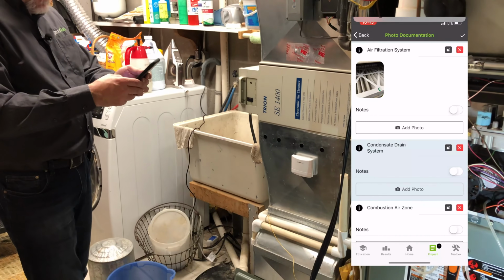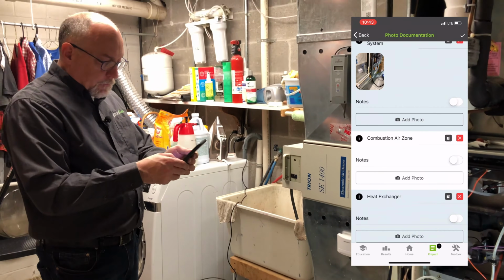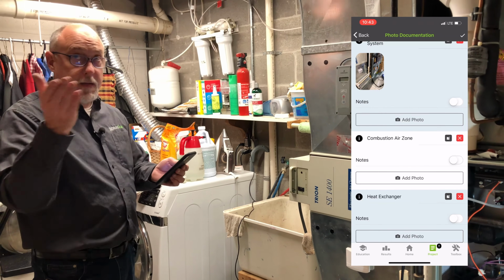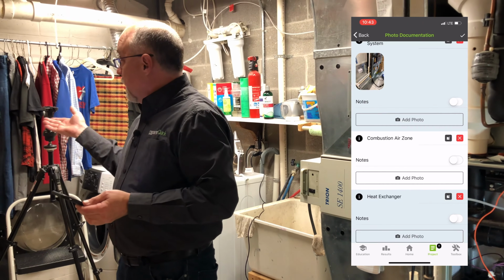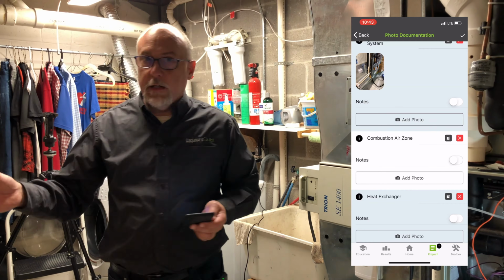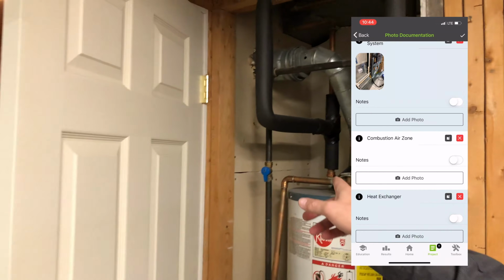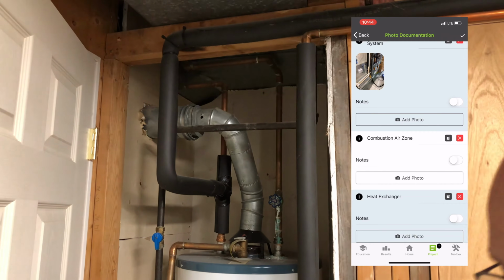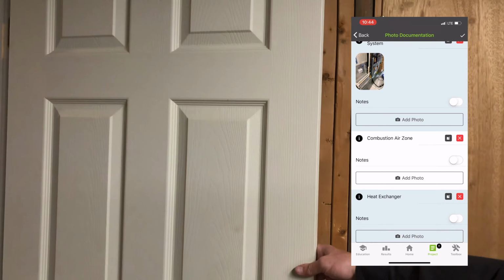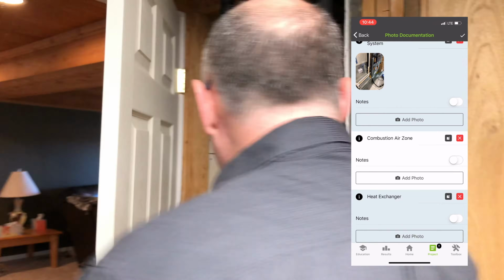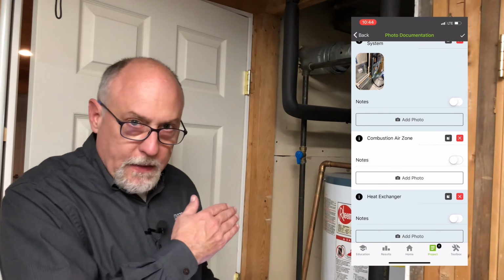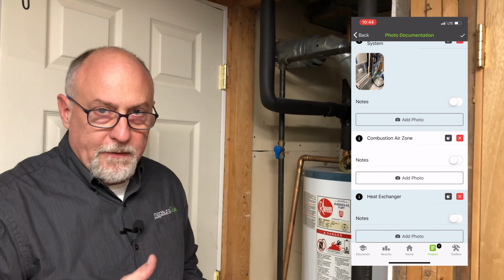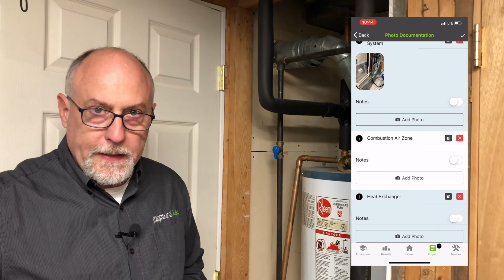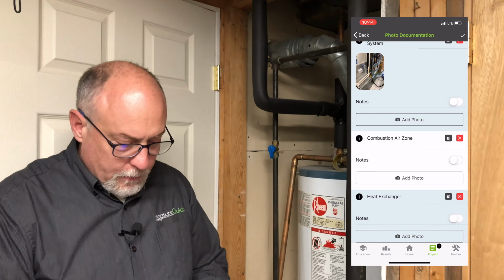Use that photo. On the combustion air zone, this is an area where we've got to look a little bit closely. We have a pretty small space here, and we also have behind here, come on in here for just a second, a natural draft appliance, a hot water tank. So, don't miss things like this. The door's open, you don't think about it, here's a hot water tank behind here, and we need to make sure this atmospheric appliance, by the time we're all done, is drafting properly, and there's no return air leaks or anything else that's going to overcome this natural draft appliance.